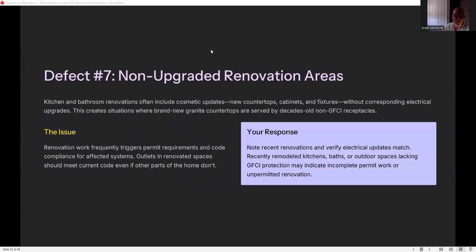Defect 7, non-upgraded renovation areas. Kitchen and bathroom renovations often include cosmetic updates, new countertops, cabinets, and fixtures, without corresponding electrical upgrades. This creates situations where brand new granite countertops are served by decades-old non-GFCI receptacles. Renovation work frequently triggers permit requirements and code compliance for affected systems.